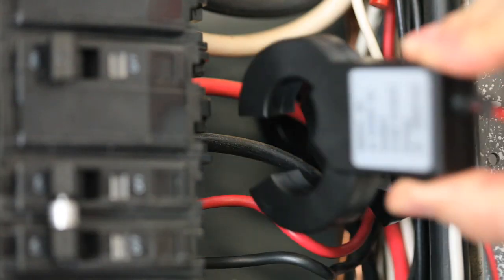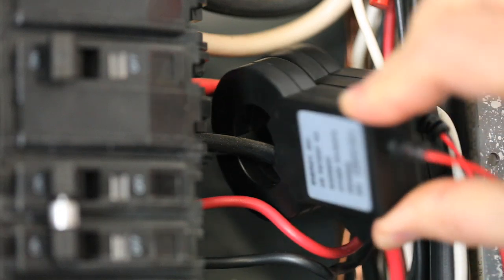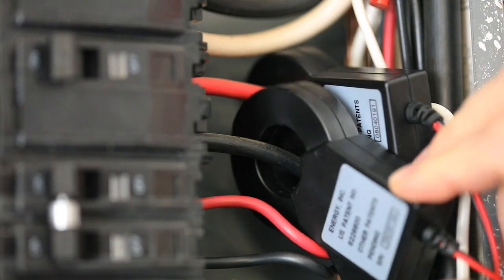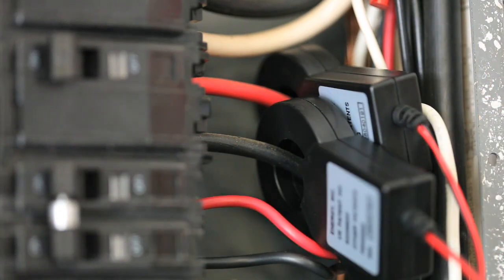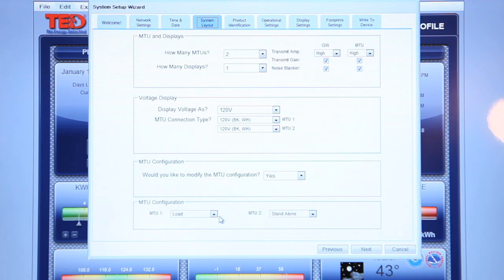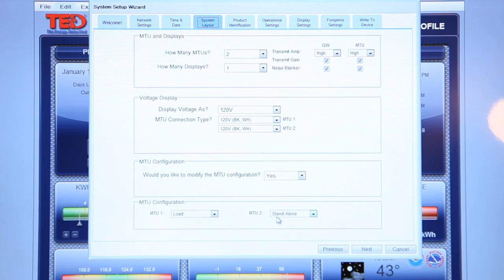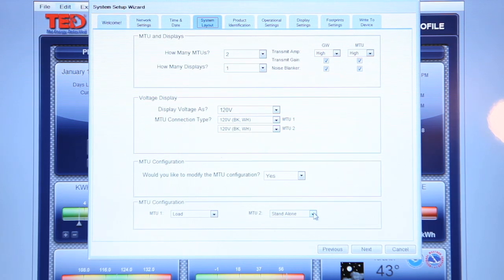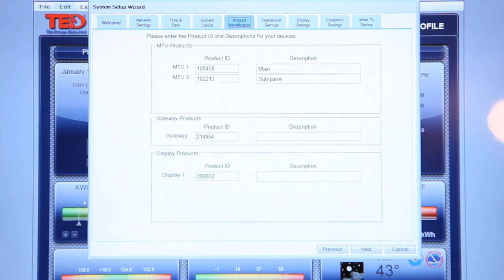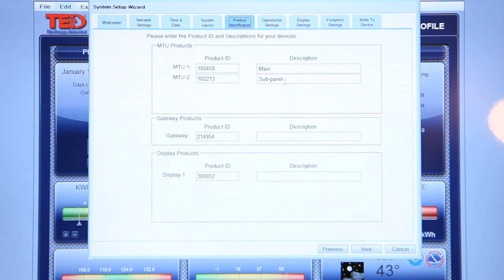If you have a subpanel that you would like to monitor independently, connect the MTU CT set on the circuit feeding the subpanel, located in the main panel. On our Footprint software, we will change the first MTU to load and the second MTU, which is monitoring the subpanel, to stand-alone. This will show us the reading of the subpanel without adding the measurement to our net reading, since the subpanel is already measured in our main panel. When entering in both MTU serial codes, make sure they correspond to the correct measurement.